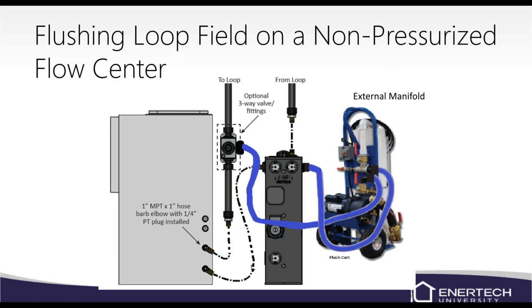Non-pressurized system, this is kind of a crazy little picture here, but on a non-pressurized, we do not want to flush through the flow center. We need to isolate it because, again, it does have PVC in it, and it has a possibility of breaking with too much pressure. So we're going to need that. It says optional 3-way valve, but we're probably going to need that. On the other side, we can hook it into the flow center and then close that valve off and just flush through the loop field.